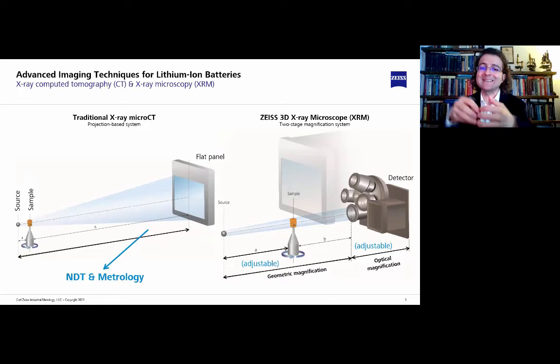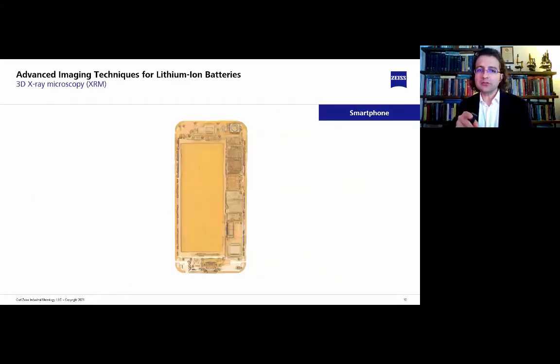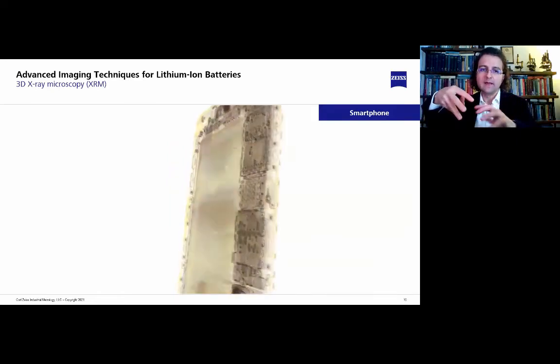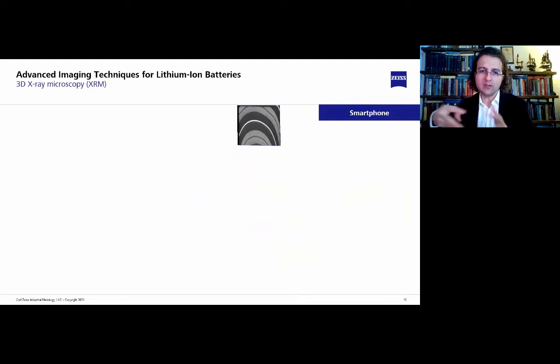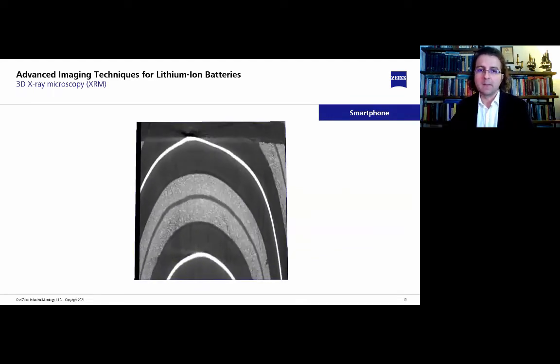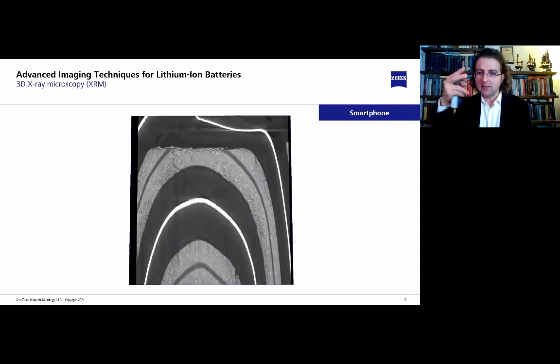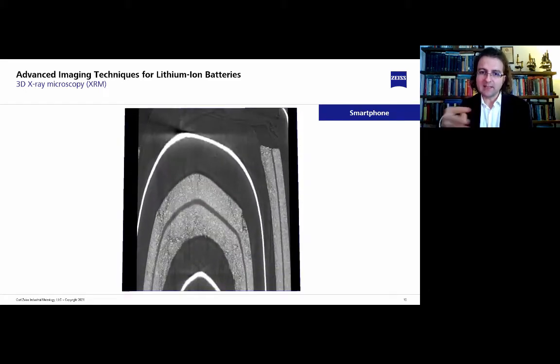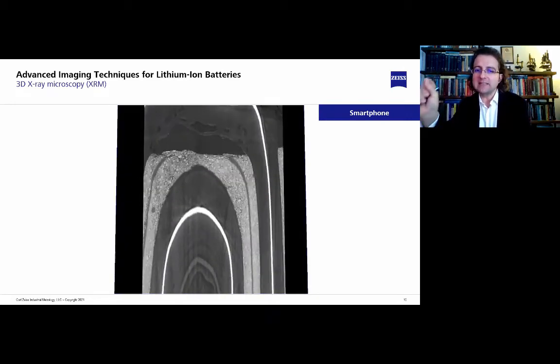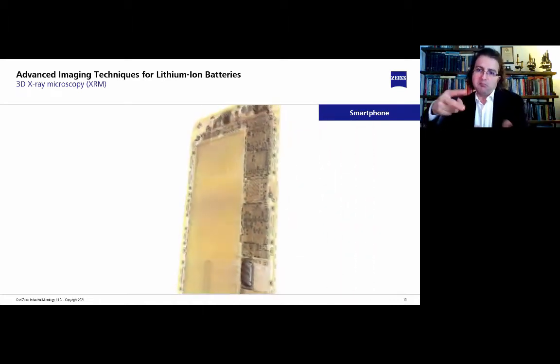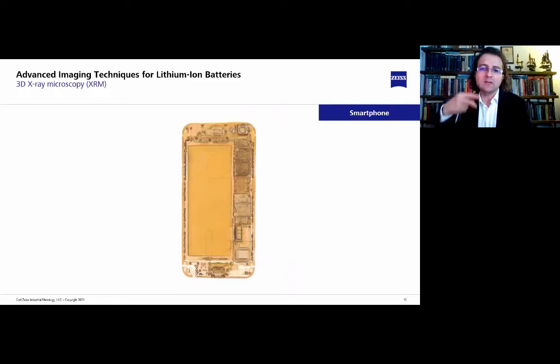But this is not a problem with the 3D X-ray microscopes we have designed at ZEISS because we have something called resolution at a distance, which we use to preserve the high resolution of the reconstructed data even for larger samples. The example shows how we can scan a full device as a smartphone without destroying it and then check for small details like the battery cells. By using the zoom lenses using the 3D X-ray microscope, we can inspect the quality of the smartphone battery, looking for any structural changes or degradations in the different layers of the battery, such as cracks caused perhaps by fatigue operations during several cycles of charging and discharging.